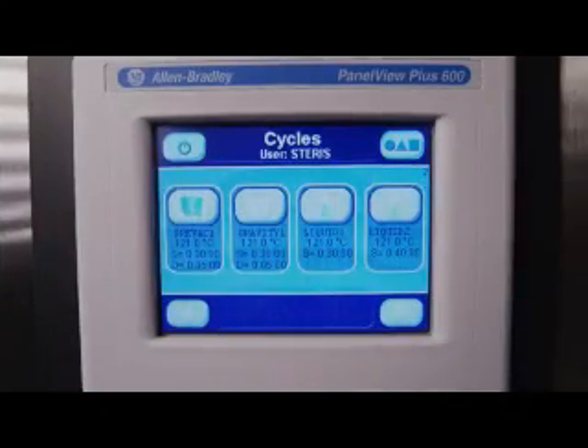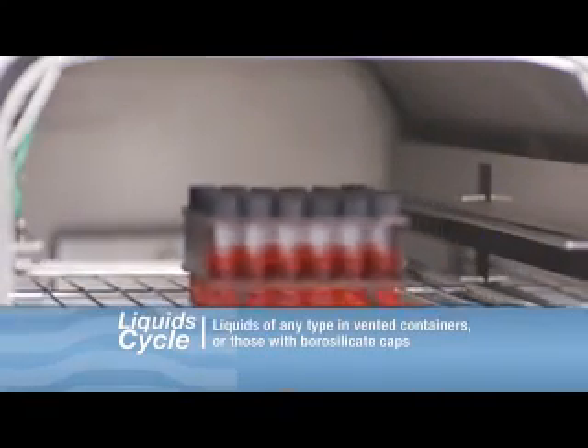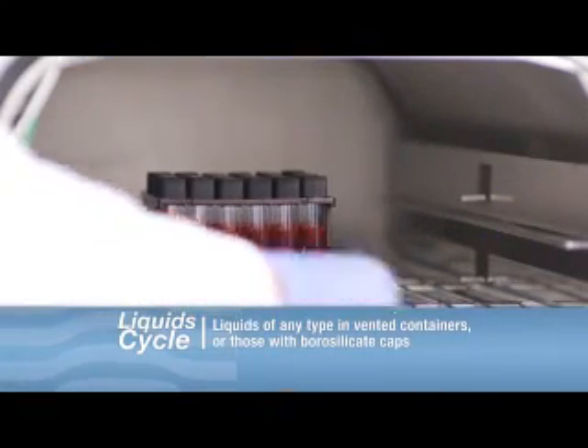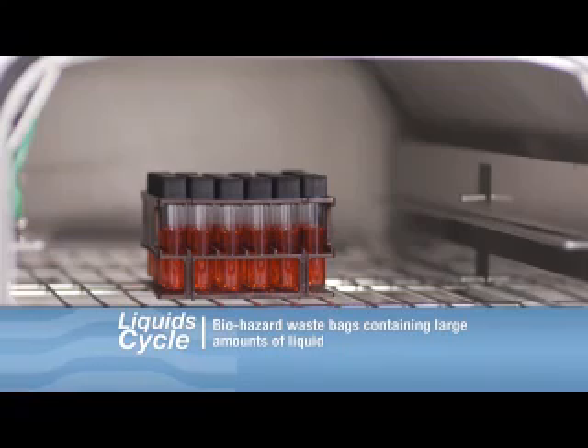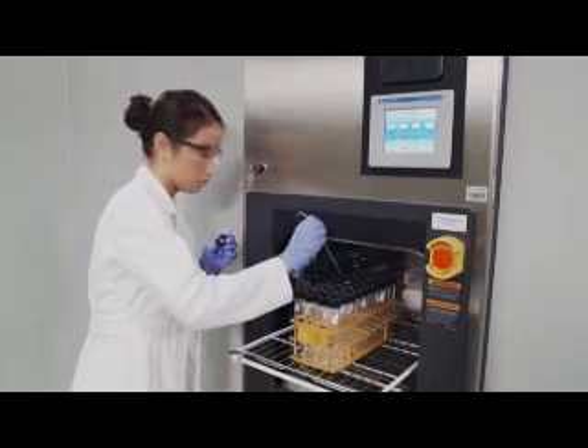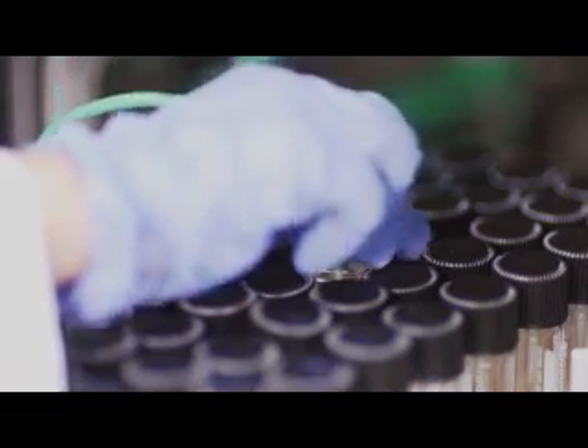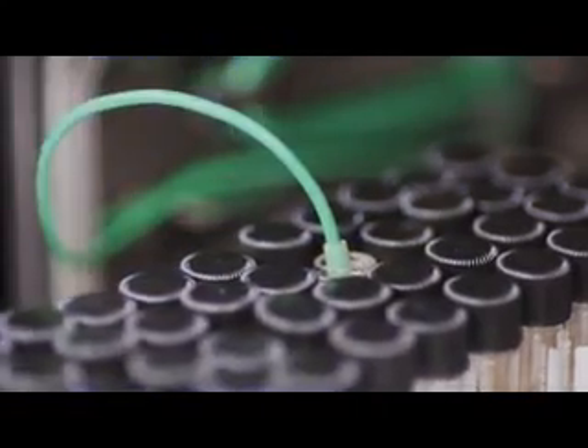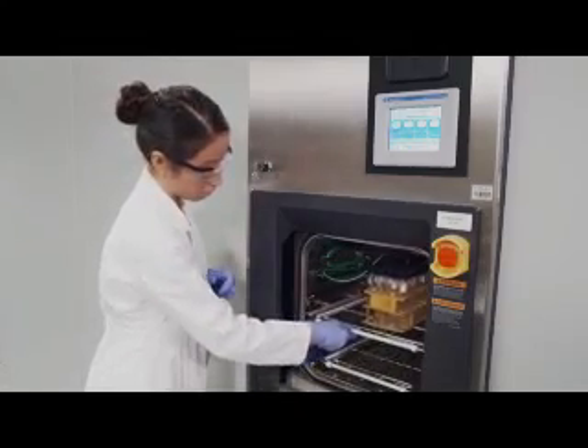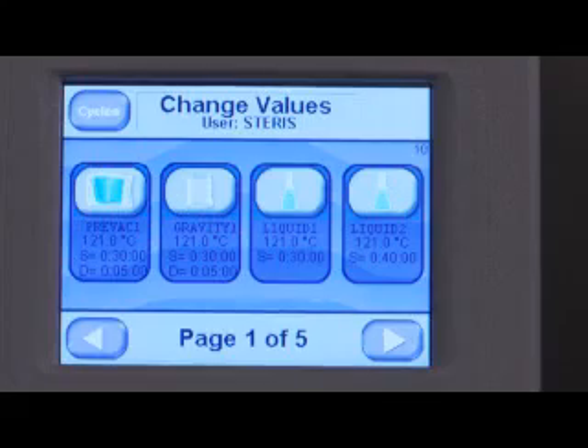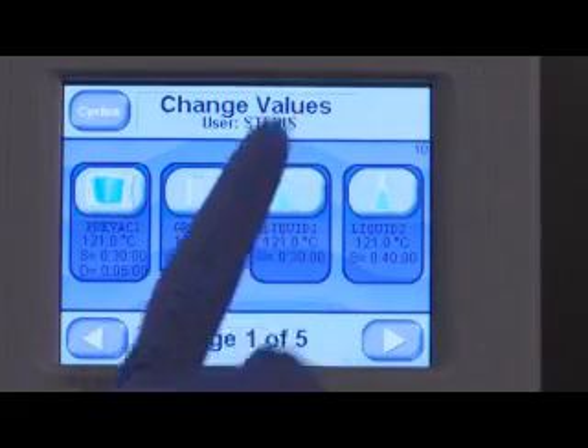Remember that the liquid cycle must always be selected when sterilizing any type of liquid. The liquid cycle contains a slow exhaust that keeps the liquids under pressure until the internal temperature is below the boiling point. Although some sterilizers use an optional load probe, most AMSCO Lab Series sterilizers use a slow-timed exhaust to ensure the liquids are cooled to a safe temperature prior to the completion of the cycle.